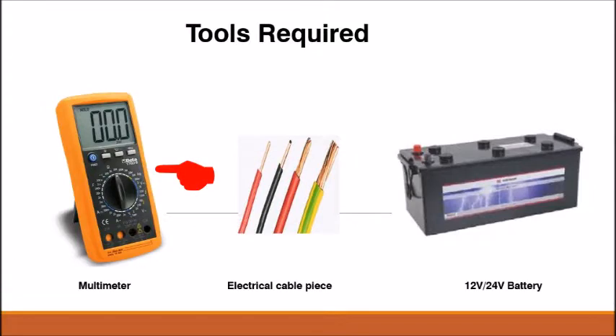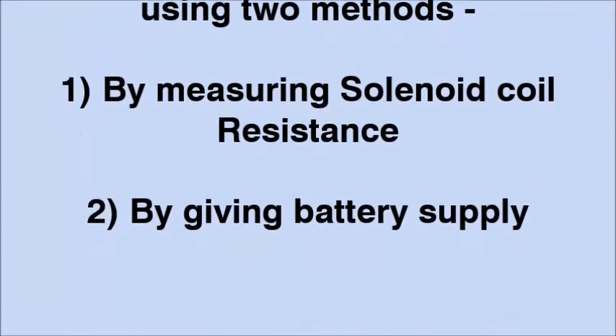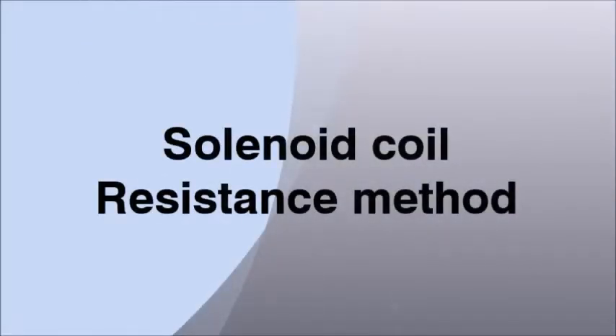To check the working of the solenoid, you will require a multimeter with resistance measurement option, an electrical cable piece of approximately 1 meter in length, and a battery supply of 24 or 12 volt depending on your generator rating. The stop solenoid can be checked using two methods: by measuring solenoid coil resistance, or by giving battery supply. First we will go through the solenoid coil resistance method.